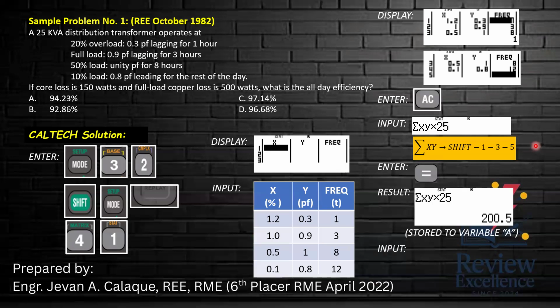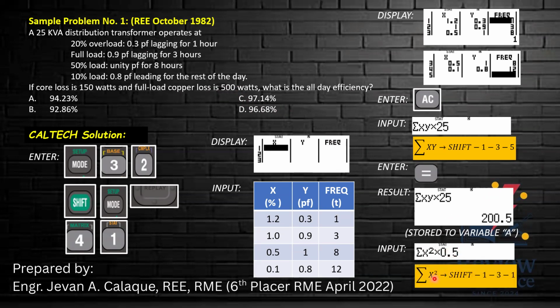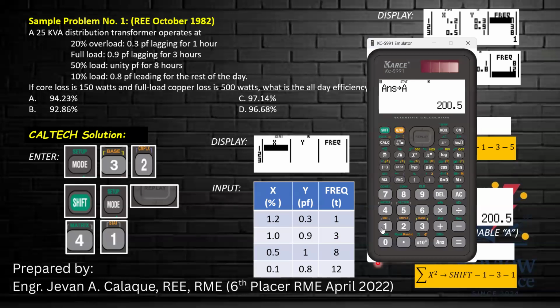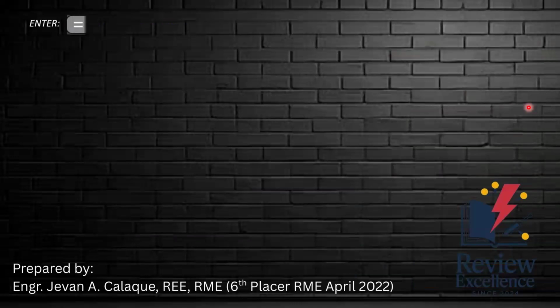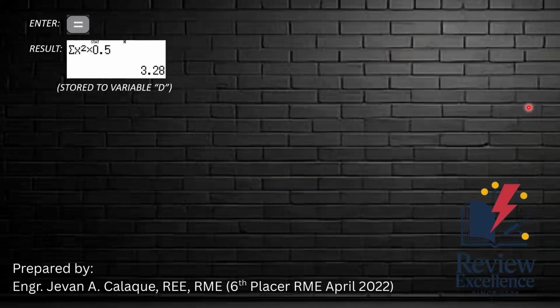The next input is the summation of x squared times the copper full load loss. The copper full load loss here is 500 watts, so in terms of kilowatts that is 0.5. So summation of x squared times the copper full load loss of 0.5 kilowatts. The summation of x squared is shift 1, 3, 1. So summation of x squared, shift 1, 3, 1, times the copper full load loss of 0.5 kilowatts. So we have 3.28. The result there, engineers, we store in variable D. Shift store variable D.